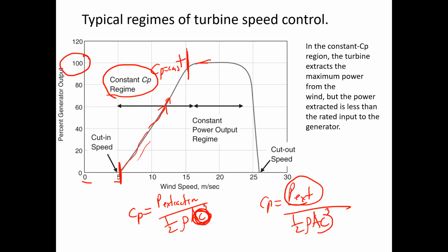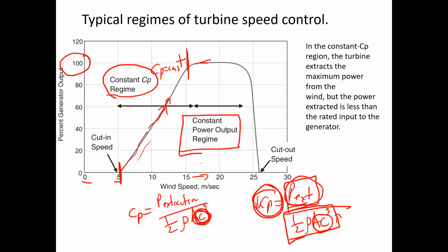The power in the air is increasing, right? So you're extracting the maximum power that you can, according to the rated generator, but the power of the air, the wind coming in, is increasing in strength as the air velocity is increasing. So what's happening is that your actual power coefficient is decreasing, but your power is constant, until you hit a point when the wind speed is getting dangerously high, and at that point, the brakes kick in, and it just stops the turbine from spinning altogether for safety reasons.